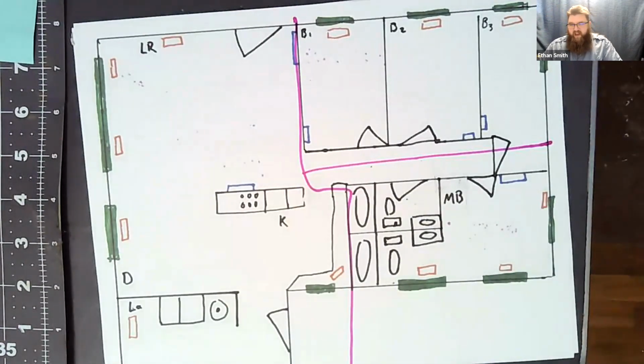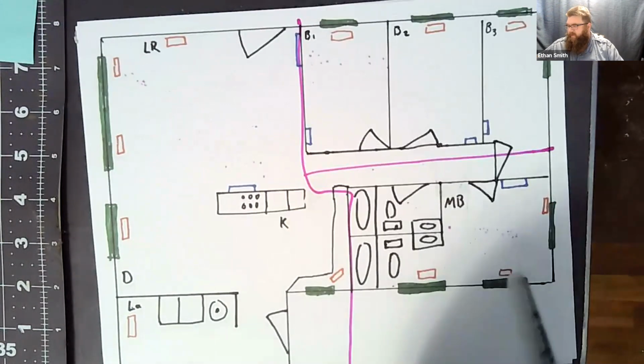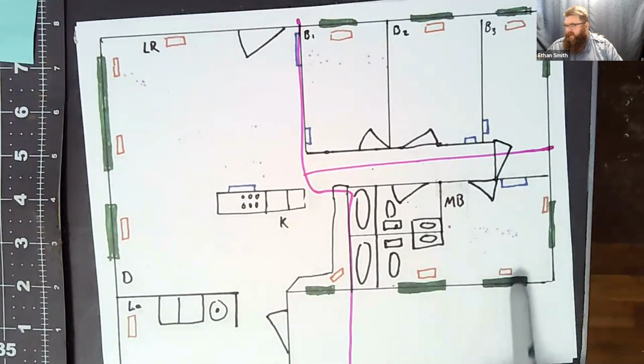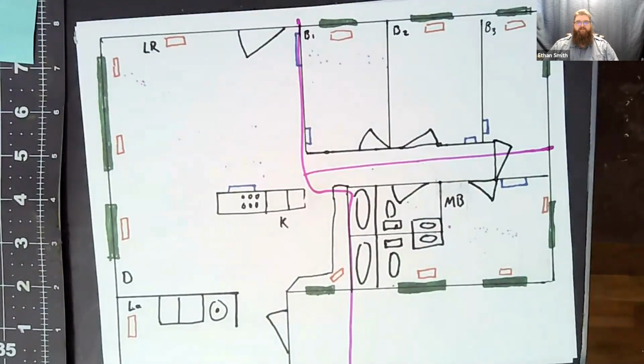When I reducted the house about 8 years ago, it was a crawl space, so I had that luxury. I knew I was going to put zoning in, so I made sure my master bedroom had a little extra air so that I could run it as its own zone and not have an excess air problem. So especially if you're building from scratch, you can accommodate those things. Okay. I ran 7-inch ductwork instead of 6-inch ductwork to help accommodate my zoning in the future.